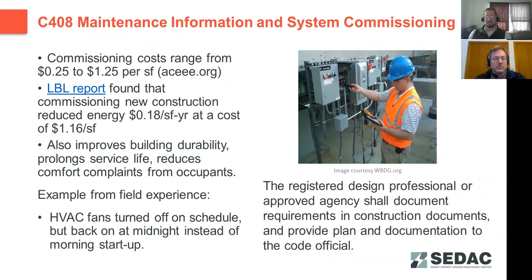But the other benefits are that it improves building durability, prolongs service life, reduces callbacks to the contractors for issues, reduces calls to the maintenance staff, and reduces comfort complaints from the occupants. One example from our experience in the field: we had a school with HVAC fans that turned off on schedule at night, but there was an error in the program logic that kicked the fans back on at midnight instead of 6 a.m. the next day. So the system ran for 6 hours overnight with no one in the building, and resulted again in a lot of excess cost for that client.